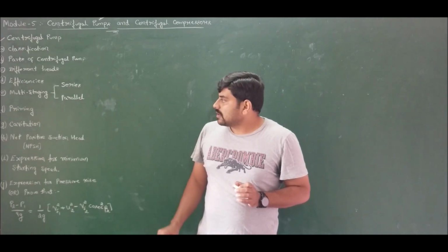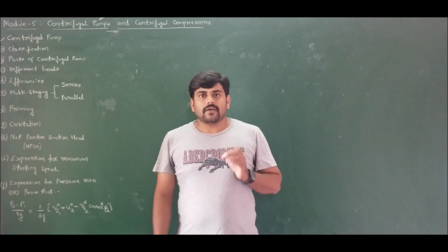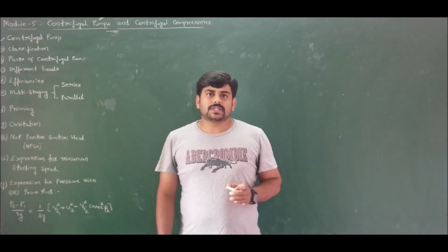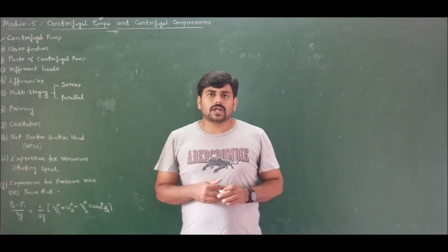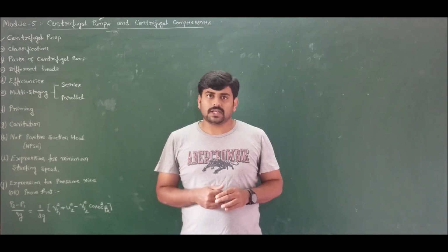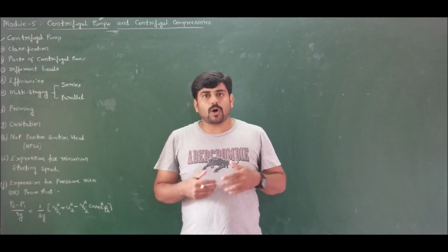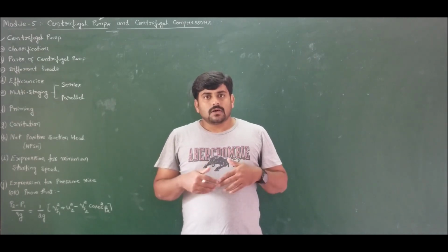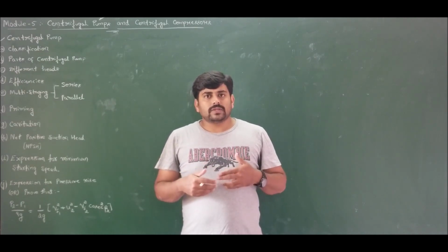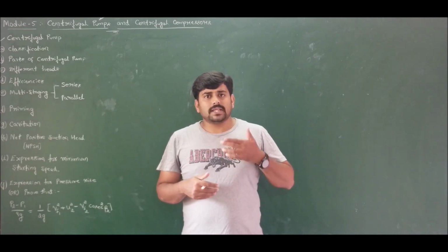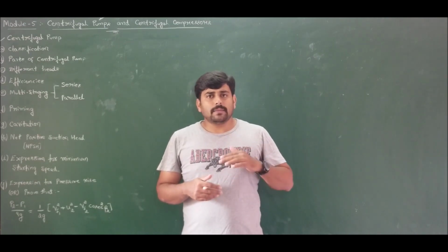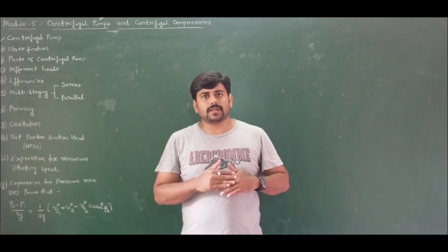Next, coming to cavitation. Cavitation is a phenomenon wherein the pressure on the suction side drops below the vapor pressure, and then water starts boiling. This boiling water moves with very high velocity towards the very low pressure side on the impeller and hits the surface of the impeller.